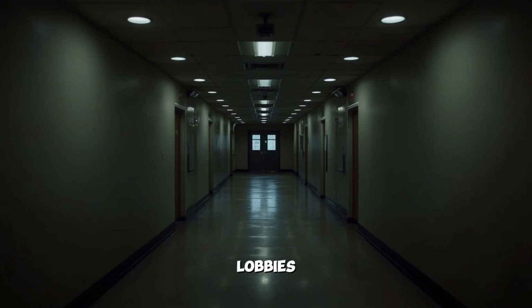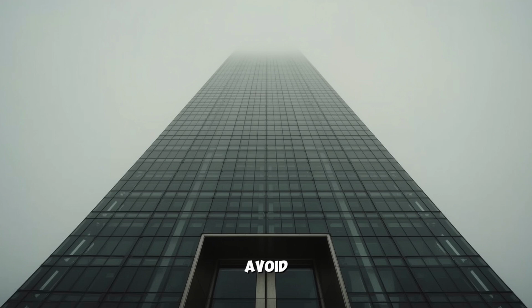Pressure readings in these lobbies now ranged from 0.14 to 0.19 inches of water column above exterior ambient, approximately double the design target. The building management system continued to interpret these readings as within acceptable operating bounds, as the alarm thresholds had been set at 0.25 inches to avoid nuisance alerts during high wind events or when multiple exterior doors were opened simultaneously during peak traffic periods. Between 8 and 8:30 a.m., as occupancy levels rose toward normal business day density, the pressure imbalance intensified in a feedback pattern that had not been anticipated in the system's programming logic.